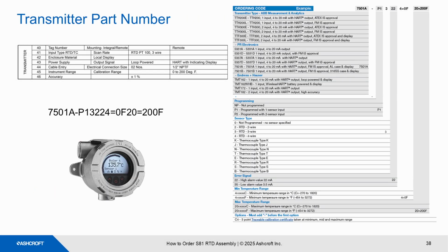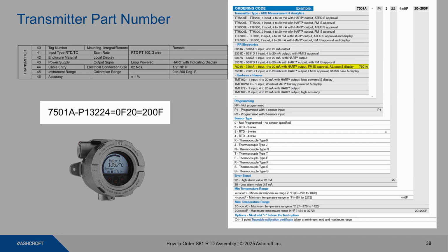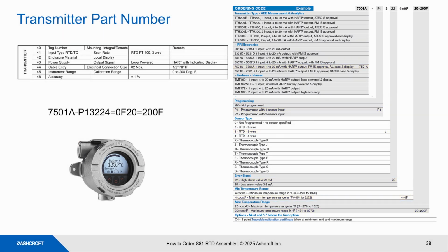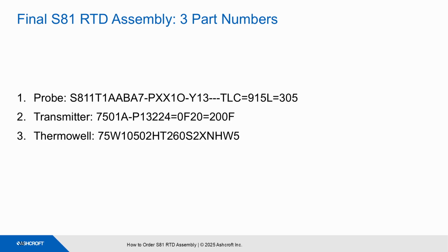To build the part number, again referring to the Ashcroft transmitter datasheet, it starts with 7501A, then there's a dash, and P1, then 3, then 22, then 4 equals 0F, 20 equals 200F. The final 3 part numbers needed for this application are shown on the screen. One for the probe, one for the transmitter, and one for the thermowell.